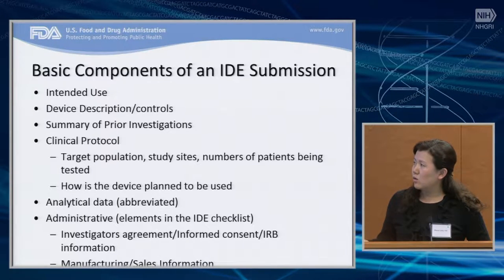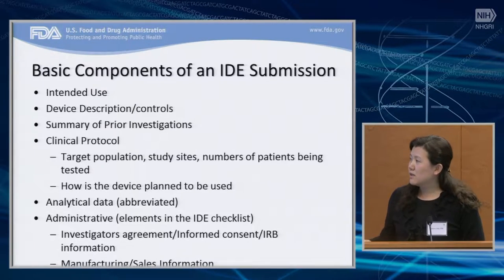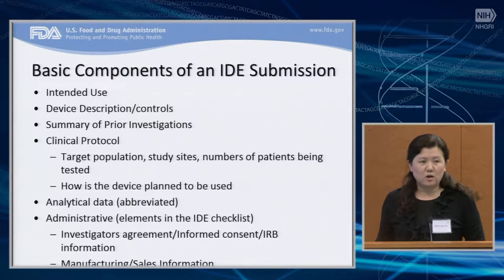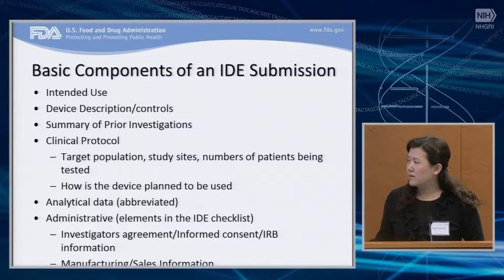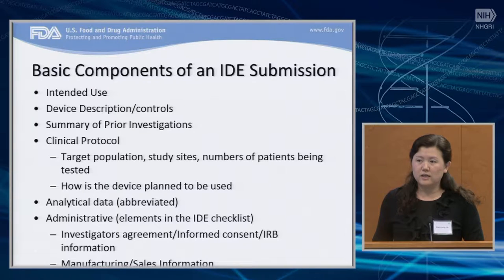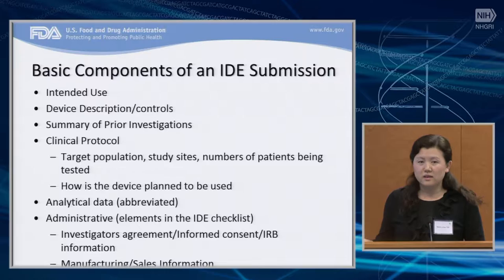You just let us know clearly how you intended to use it, what components it has, and also how it works to generate the test results. In the clinical protocol, we like to see what the targeted population is, how many clinical sites need to be used to enroll patients, and then how many patients will be tested using the device. How the device is planned to be used in the clinical trial will help us understand your device and understand your risk of using it in the clinical trial.